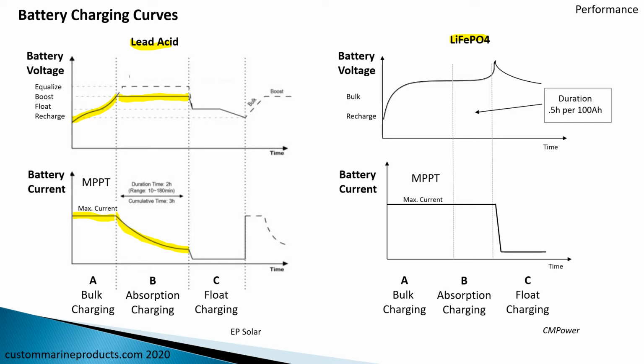So over a period of time, we really can't get as much current or power into the battery as it becomes more inefficient. Then once it's charged, we need to go into a float mode to give it a slower charge for that last 10%. On the other hand, a lithium iron phosphate will come up to charge very quickly, up to voltage, and maintain that constant voltage all through the charge process. And it will accept, and this is the key, a constant current, maximum current, all the way through the charge process until its full current is reached.